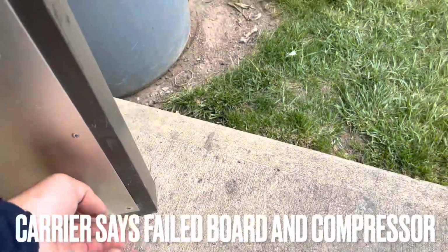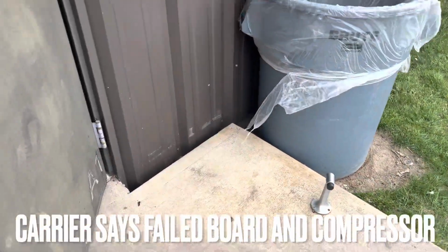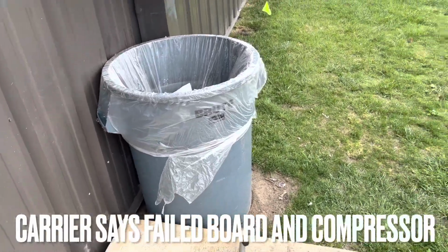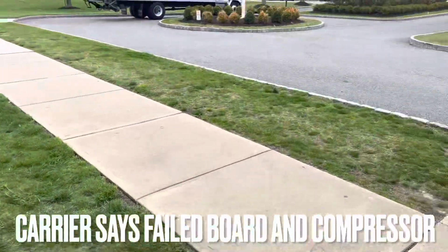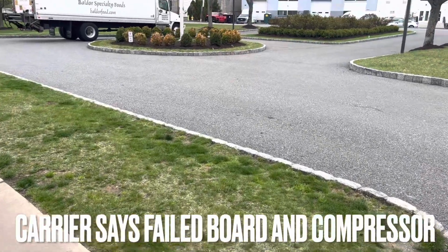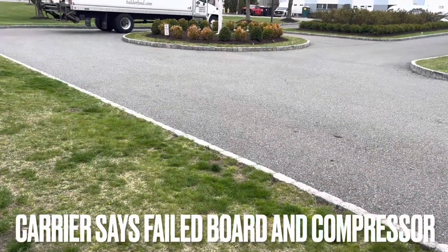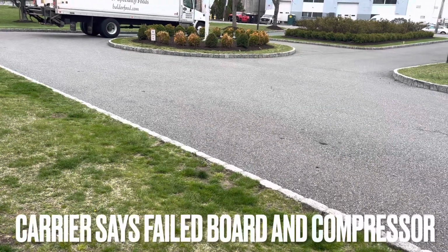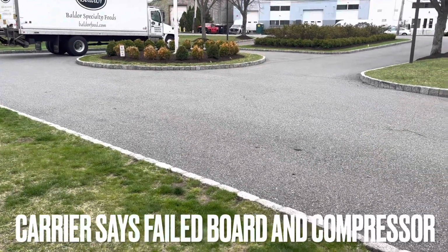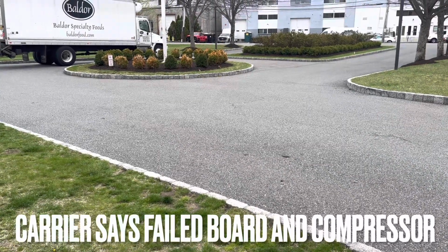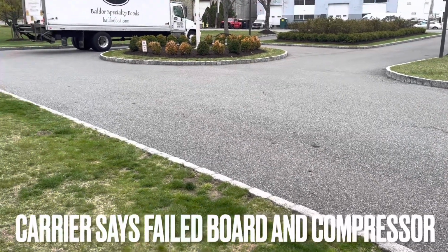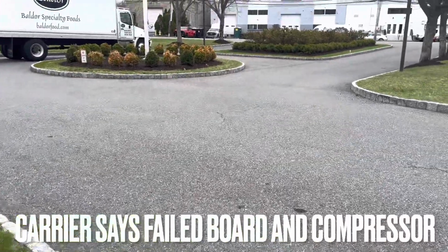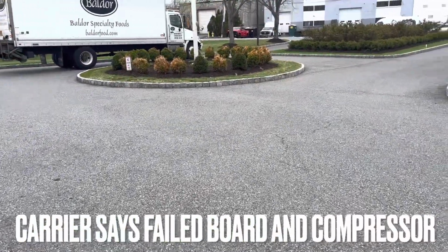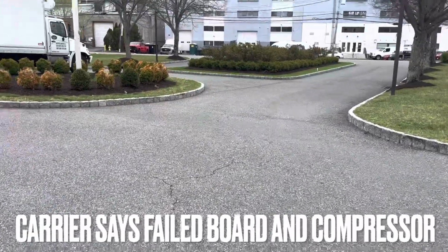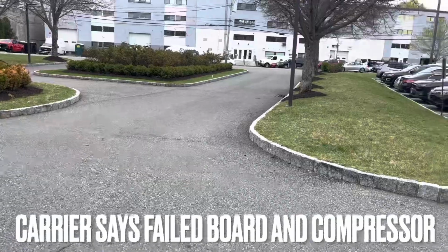Guys, if it was me just diagnosing without speaking to Carrier, I would start with the board. But Carrier says it's the board and the compressor. I understand the inverter side, the ohms were way off from 0.203, but can't that just be the control board? Because that's where I was checking, coming from the board. But again, the compressor comes into that board. That was her reasoning. It might be because it's 9 years old and she knows it's out of warranty. I have no idea, and I say she when I'm talking about tech support. So whatever, it is what it is.